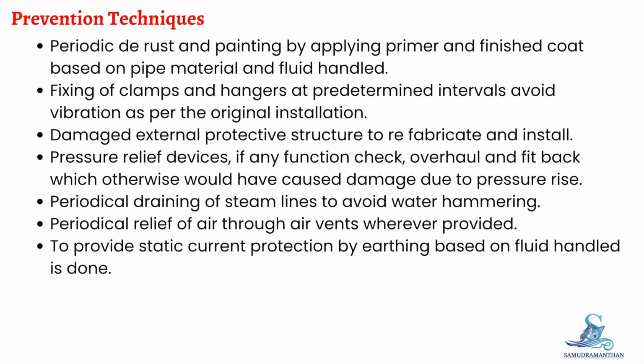Prevention techniques. Many pipe failures can be avoided through proper preventive maintenance. Pipes should undergo periodic derusting and painting, using suitable primers and finished coats based on the pipe material and the fluid being handled. Clamps and hangers must be fitted at predetermined intervals, exactly as per the original installation, to prevent vibration-induced failures. Any damaged external protective structures should be refabricated and reinstalled without delay.